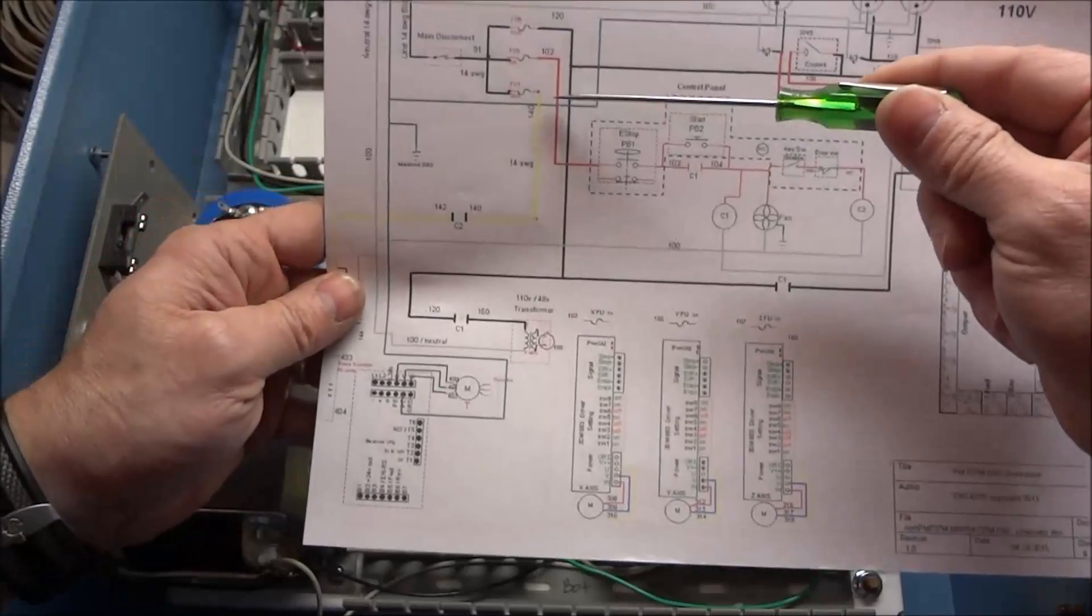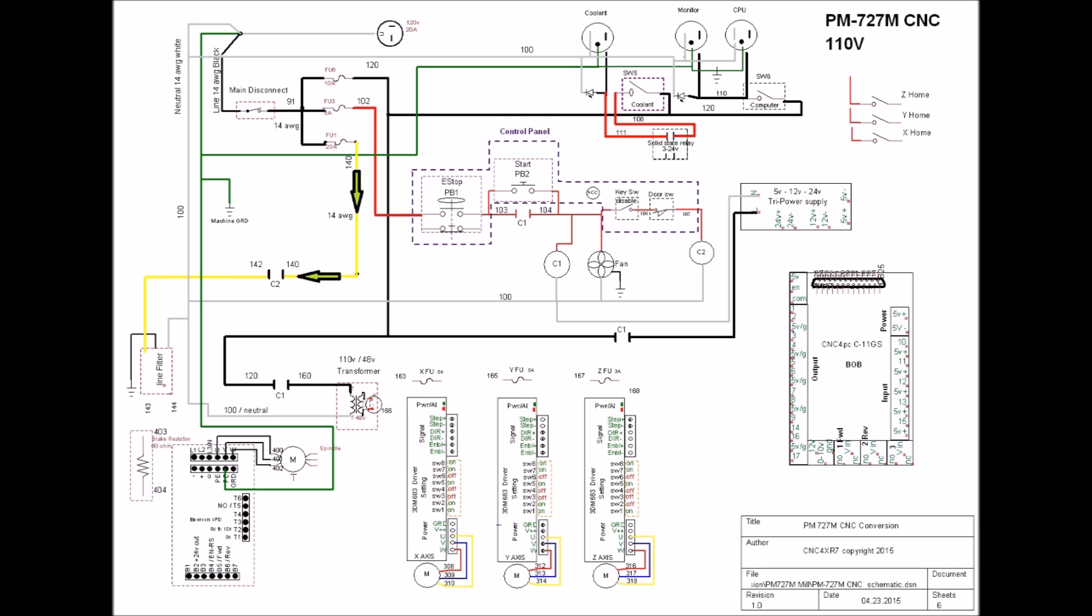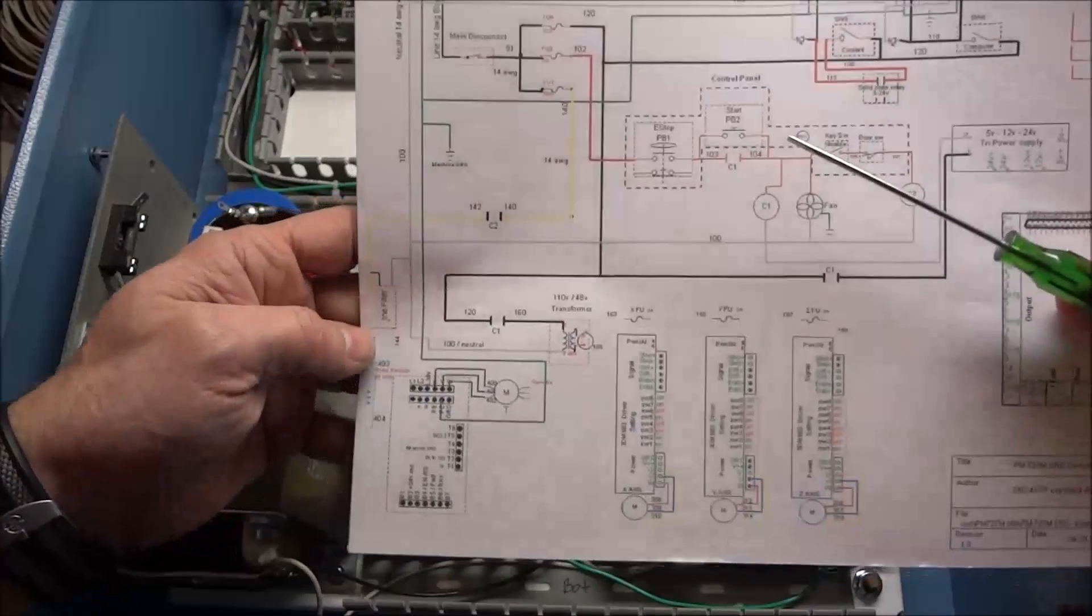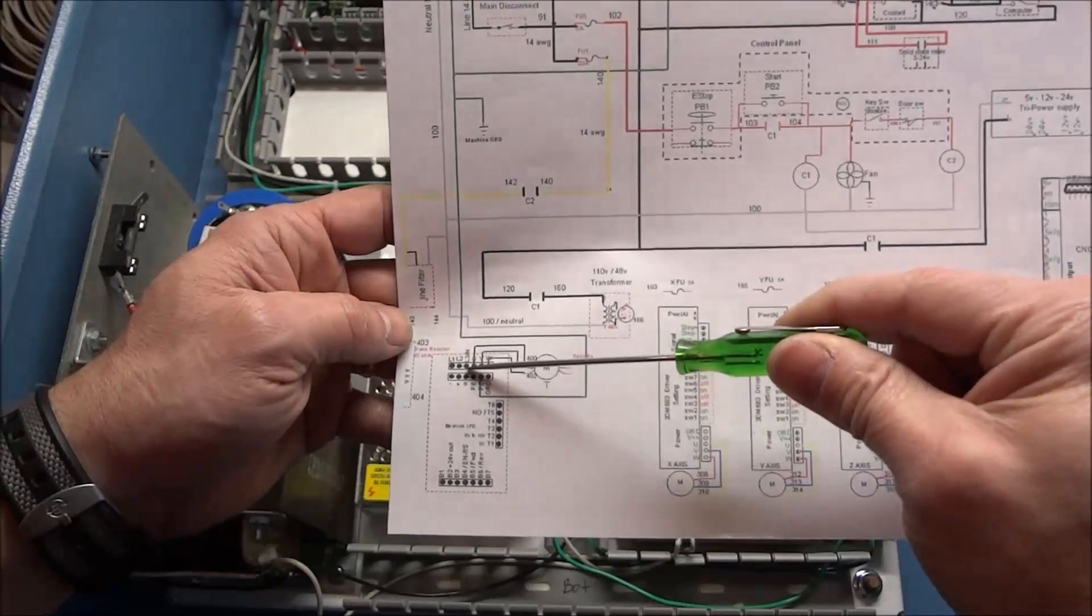We can now start working on fuse 1 and we want to bring power to contactor 2, a normally open set of contacts. This will be wire number 140 and this will supply power to our line filter and to our VFD.